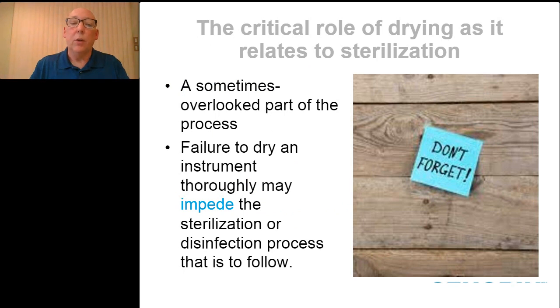Now, drying is, as I mentioned, a critical part as it relates to sterilization. It absolutely is. Drying needs to be a conscious part of sterile processing, just like washing, just like sterilization, and other processes. It has sometimes been an overlooked part of the process. If you think about it, during the day you're busy, those of you who have drying cabinets, placing devices, trays, containers, and items in your drying cabinets, opening and closing the doors all day. It becomes kind of second nature and just part of the environment, right? But we want to make sure that we're giving conscious thought to those intricate, complex devices. Are they truly dry? How are they being dried? Just like we do with washing and sterilization. Because just like the slide says, failure to dry an instrument thoroughly may impede sterilization or disinfection processes that are to follow.